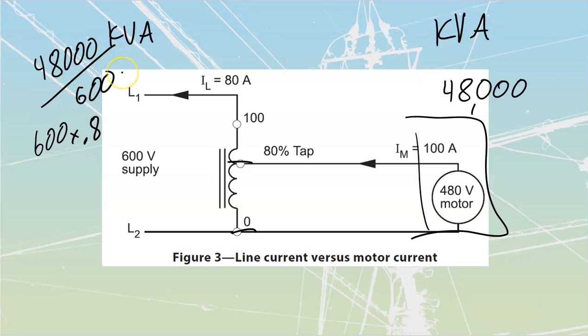Now this whole calculation we're doing over here is a single phase calculation, right? It's pretty obvious, there's only a single phase operating. That's why we're not using root 3 inside any of these calculations. But by the time we go to a 3-phase one, we will have to start applying those root 3s into it.